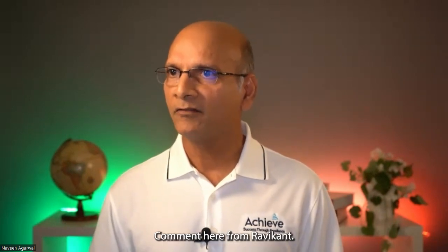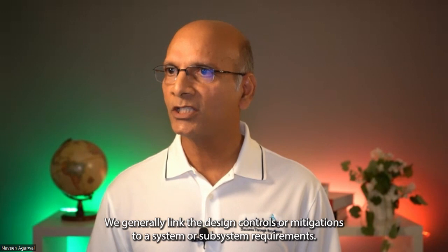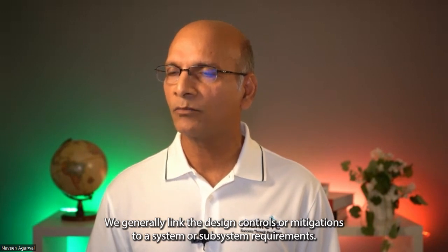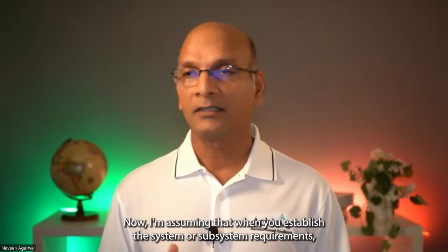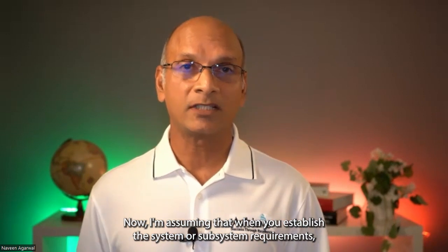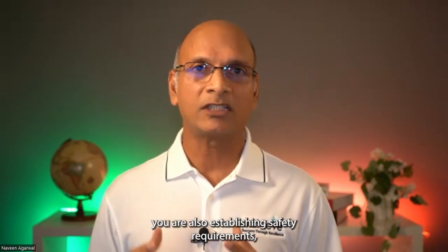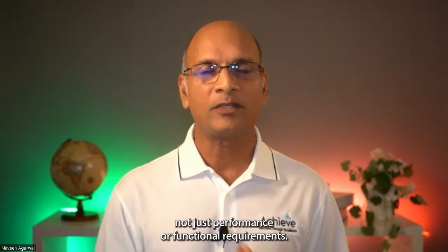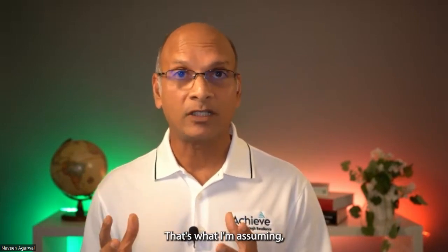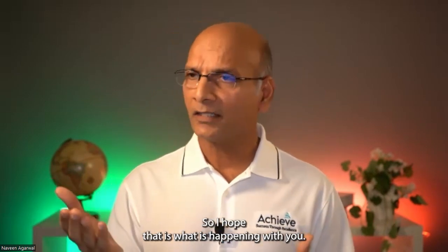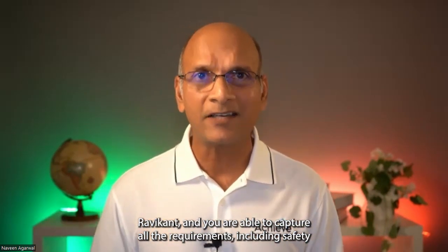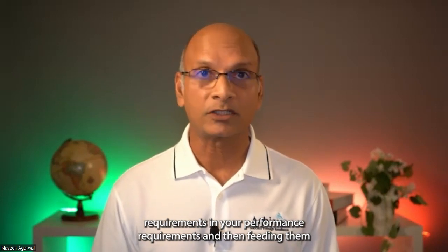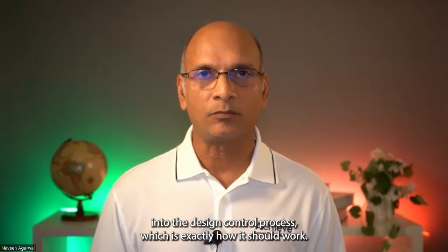Comment here from Ravikant. This is not a problem for me. We generally link the design controls or mitigations to a system or subsystem requirements. That is absolutely the right way to do it. Now, I'm assuming that when you establish the system or subsystem requirements, you are also establishing safety requirements, not just performance or functional requirements. That's what I'm assuming, because if you are doing that, then you have tight connectivity.